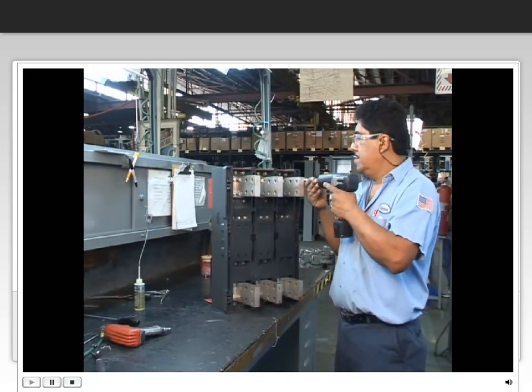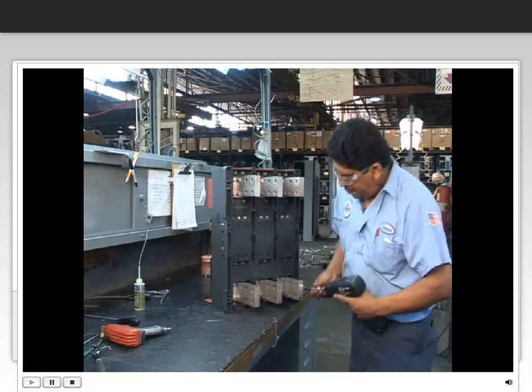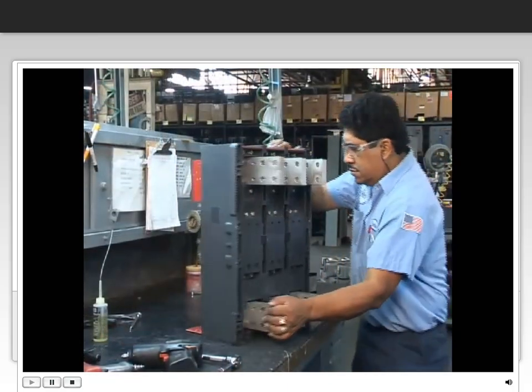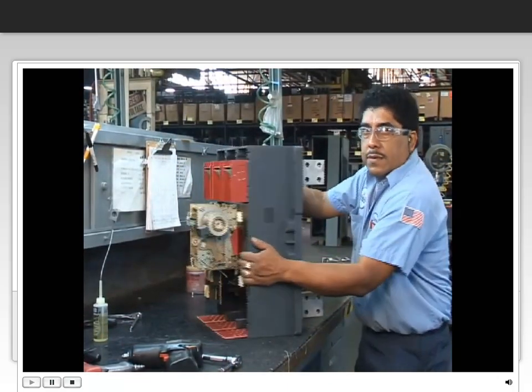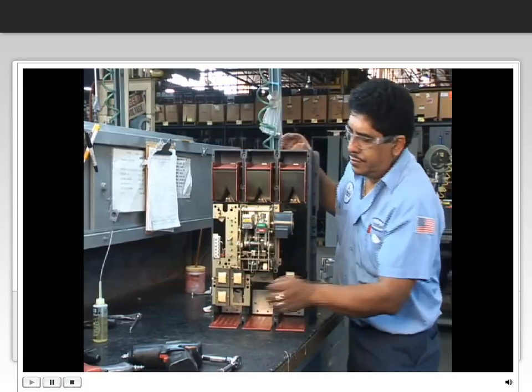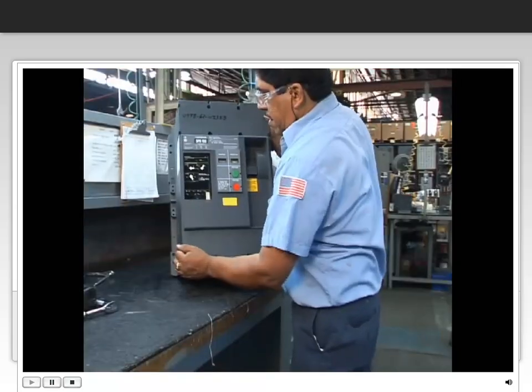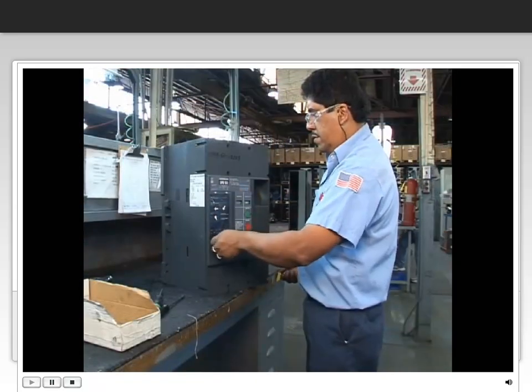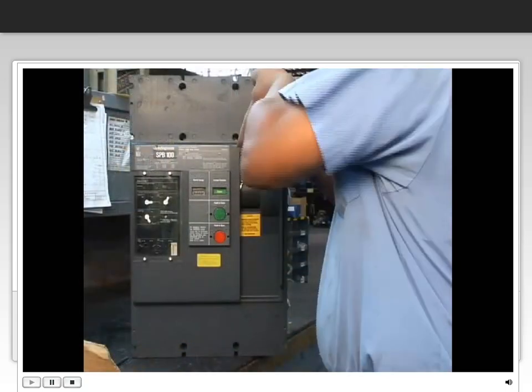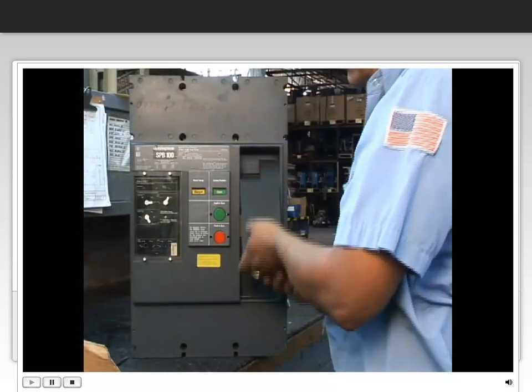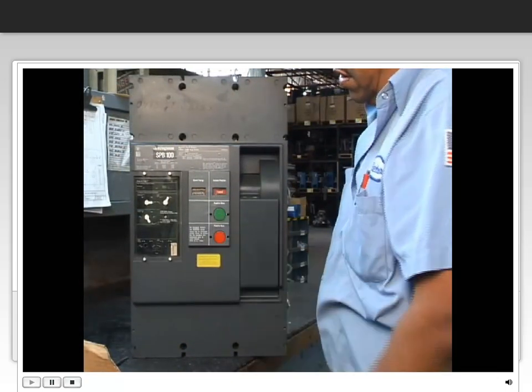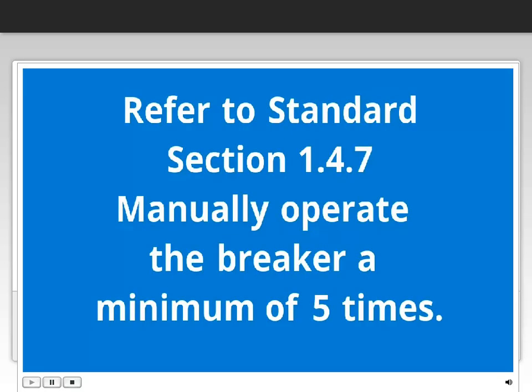All the T-connectors are reinstalled. The covers for the breaker and the trip unit are replaced. Then the technician manually operates the breaker to make sure the mechanism is tight and operation is smooth. This should be done at least 5 times manually and 5 times electrically.